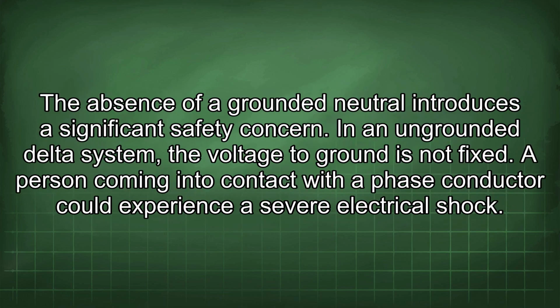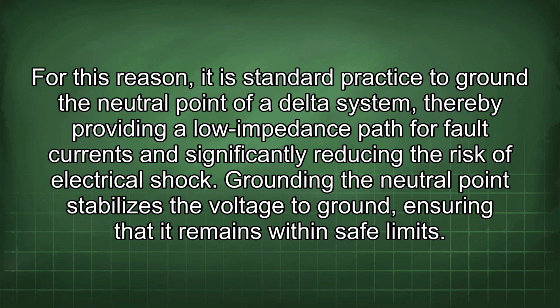The absence of a grounded neutral introduces a significant safety concern. In an ungrounded delta system, the voltage to ground is not fixed. A person coming into contact with a phase conductor could experience a severe electrical shock. For this reason, it is standard practice to ground the neutral point of a delta system, thereby providing a low impedance path for fault currents and significantly reducing the risk of electrical shock. Grounding the neutral point stabilizes the voltage to ground, ensuring that it remains within safe limits.